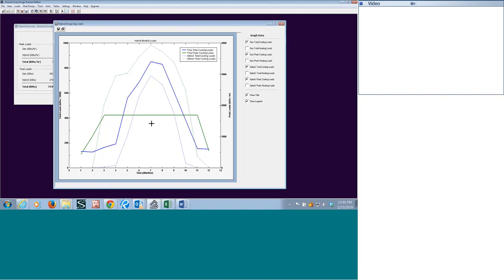We've even seen some cases where after 5 years the system was shutting down, and they pulled out an air filter, and it was all caked with dirt, and of course the ductwork was contaminated, and so was the DX coil. But we have found things that simple that could have been addressed without getting lawyers involved. But when you see something like a ground loop that's severely undersized, that can get pretty expensive, and adding auxiliary cooling or heating can be an issue. But again, this graphing feature with GLD is pretty handy, because now you can share with the client and anyone associated with the project what the impacts are and what you're doing to resolve the issue.